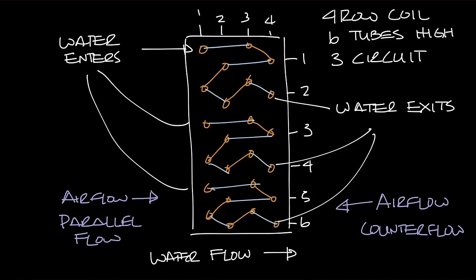So this is a drawing from last week and if you remember I had a three circuit water coil. As I look at this now I realize that I show the water entering from the top and exiting out the bottom, but actually you want your water to enter through the bottom.